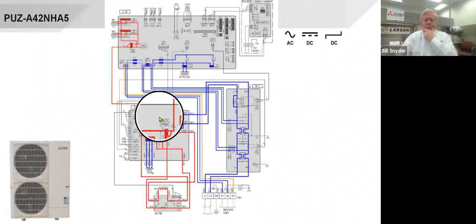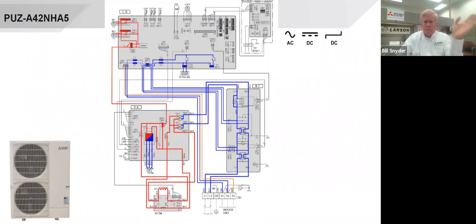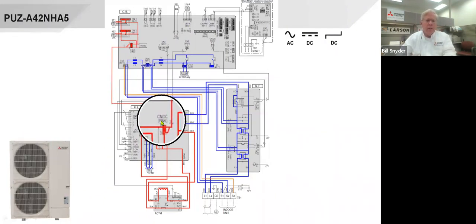The DC voltage also comes to this, it says CNDC pink. Hopefully you can see that. It's a hot pink connector that's on the board, and they use the same pink connector on all of our equipment across the board. So anytime you see that, it's an indication that that's the 300 volt DC signal. CN just stands for connector. You'll see that throughout Mitsubishi's terminology. CN is connector, and DC just means that it's direct current coming out of there. This connector has 3 pins on it, pins 1, 2, and 3. We're only using pins 1 and 3. Anytime you see that 300 volts DC, we try to separate that power because it can arc, so they leave a little space between them.